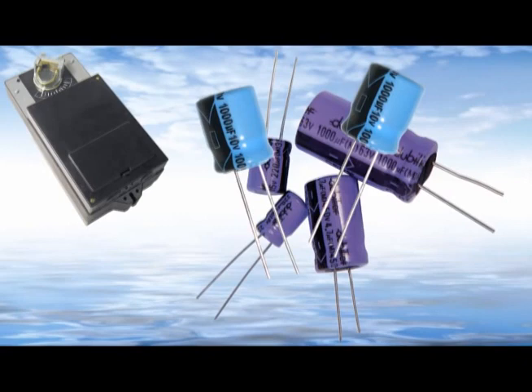Capacitors are electronic devices that store electric charge and require very little current to remain continuously charged whenever power is applied. When electric power fails, the charge in the capacitor is used to drive the actuator back to its home position.